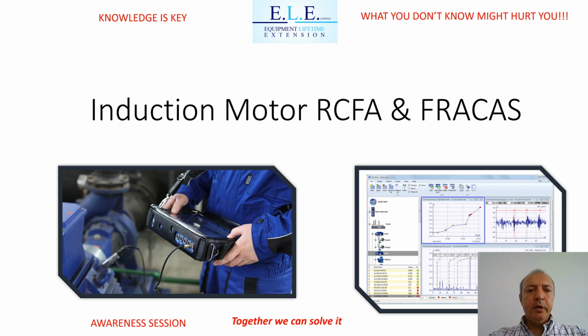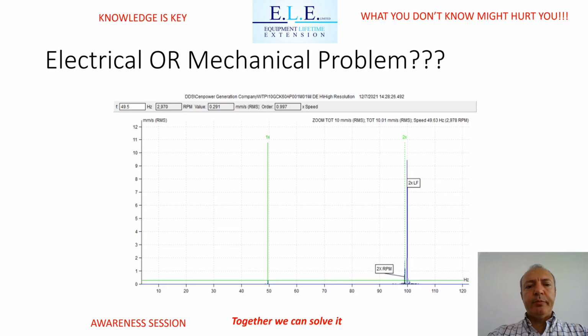Hello and welcome to this awareness session related to induction motor root cause failure analysis and corrective action system. In today's example, we will consider a vibration spectrum that is showing a magnetic field at 2-times line frequency, indicating that there is a problem in the stator.